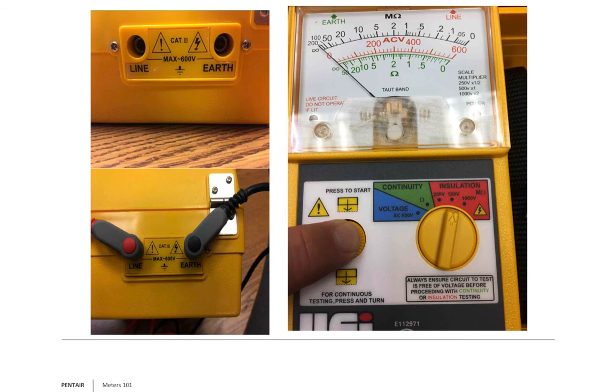This is an analog megohm meter. Some guys say there's no such thing, and I say, yes, there is. You can see here it gives you the instructions on how to set it up on the back for your probe set. This one has coloration for the different lines you want to read. Ohms, with the horseshoe or the omega sign, is always in green. When I push the button, this one too goes up to 50 million ohms. It's hooked up to that same motor that was measuring 2 gigaohms on the digital, so that's why the meter doesn't even fluctuate.